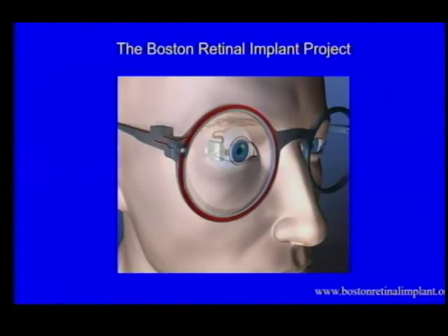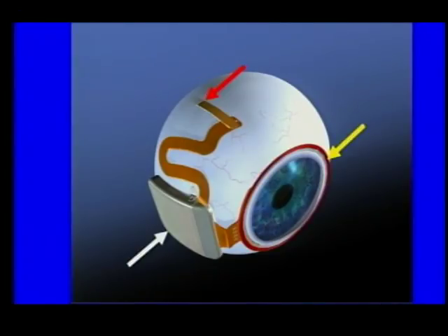We can send information in, and from every electrode in real time, we can know its behavior because there's also reverse transmission of wireless communication. By the way, you wouldn't see this device when it's implanted on a human. This is just schematically. So now let's look at the device itself. So I told you we took a very long time to scale up the number of electrodes. Well, part of that is you're going to need a lot more power. So if you put a coil on the side of the eye, you have a pretty significant limitation in terms of how much power you can deliver.